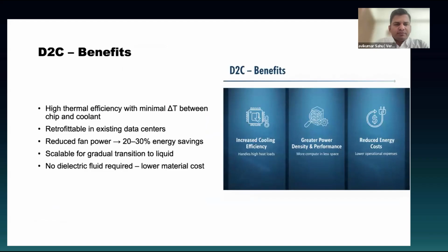Talking about the benefits, the benefit of direct to chip is that it can be easily configured into your existing data centers. You can convert 2-3 racks into liquid cooled racks and use them in your traditional or conventional data centers. Since we have reduced fan power by 70 to 80%, savings may be 20 to 30% in terms of overall power consumption. As we discussed, we can gradually transition to liquid. If any customer wants to switch to liquid cooling, D2C is the best choice to start from. And since no dielectric fluid is involved, it is cheaper in terms of capital cost.